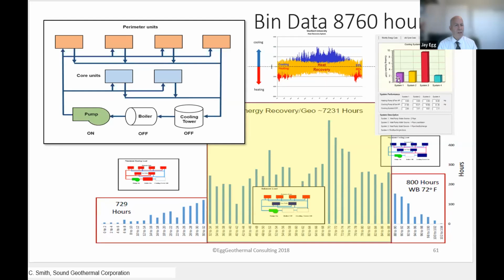And what that does, in a coefficient of performance rating, is if you're taking heating equipment, heat pump equipment, and cooling equipment, and you're putting them into the same energy network, you end up taking equipment that's rated at a 3 or 4 coefficient of performance. And when those two pieces of equipment are sharing energy one with another, their coefficient of performance goes up to 9 or 10, meaning 900 to 1,000% efficient because they're sharing energy one with another.